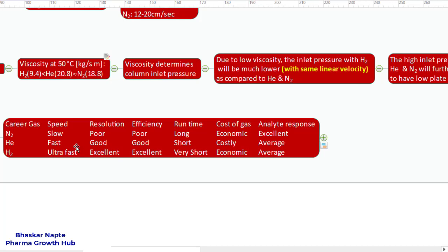If you look at the speed, nitrogen is going to give the slow speed. Helium is going to give the fast speed, but hydrogen results in ultra fast chromatography. Resolution is poor with nitrogen, good with helium, and excellent with hydrogen. In case of efficiency, it's poor with nitrogen, good with helium, but excellent with hydrogen. What about the runtime?